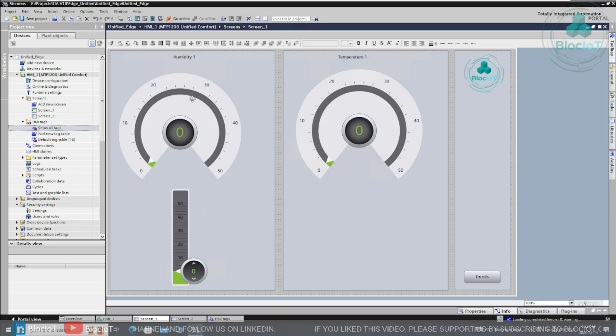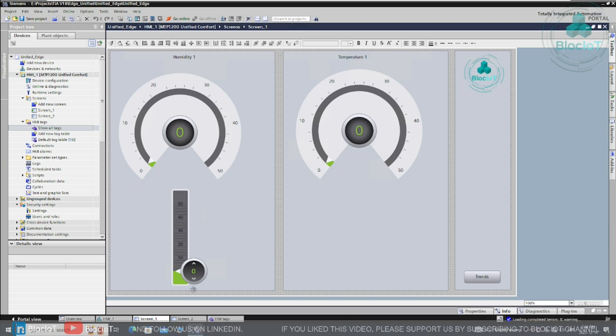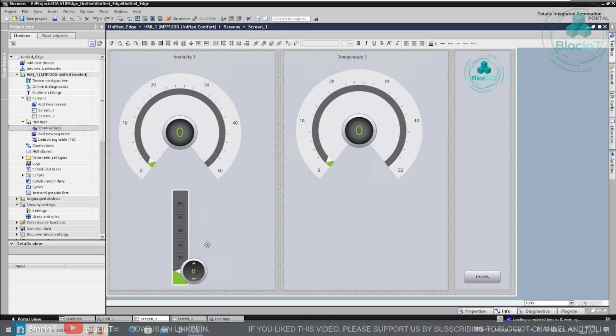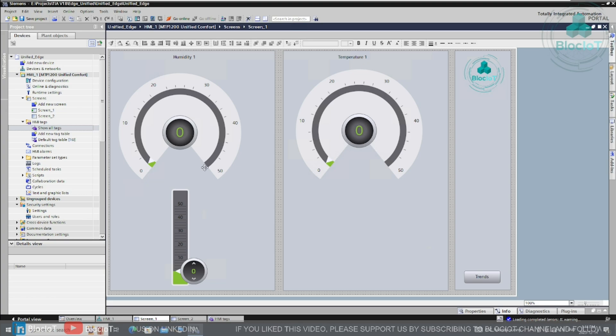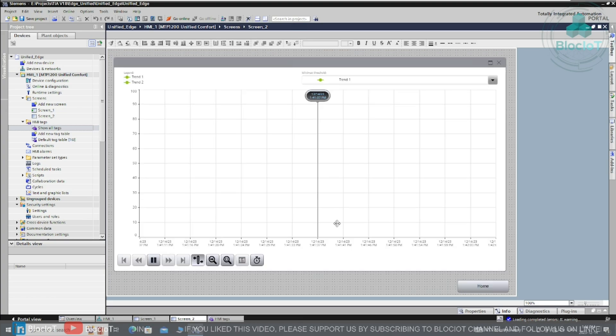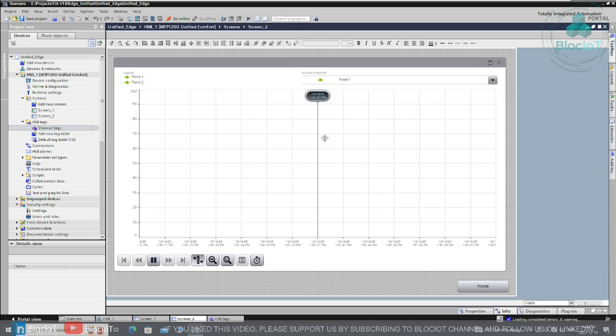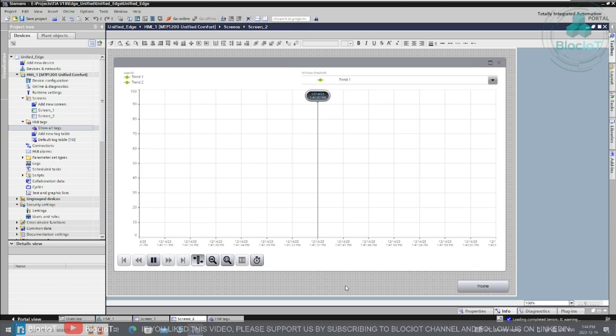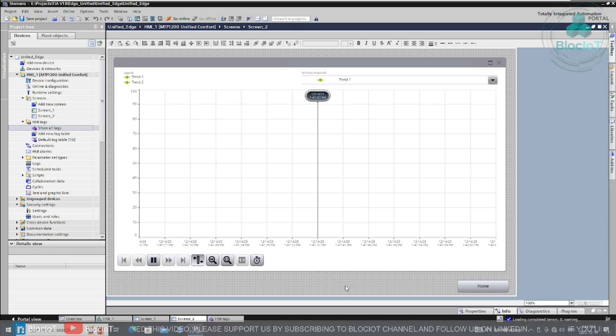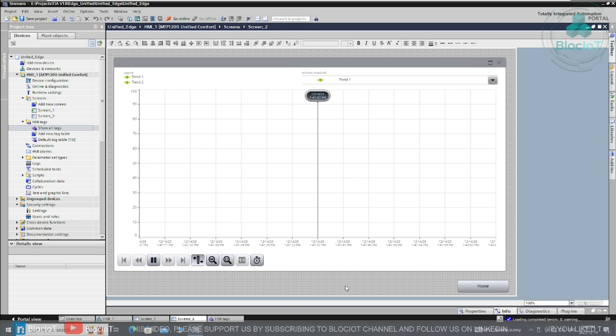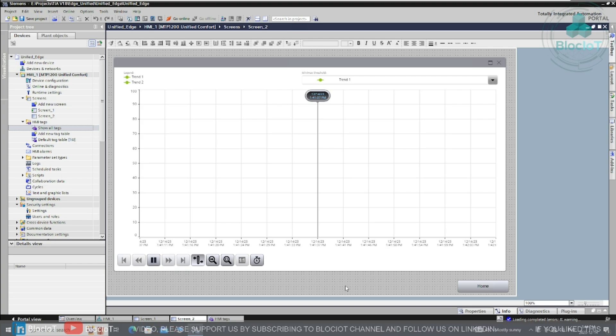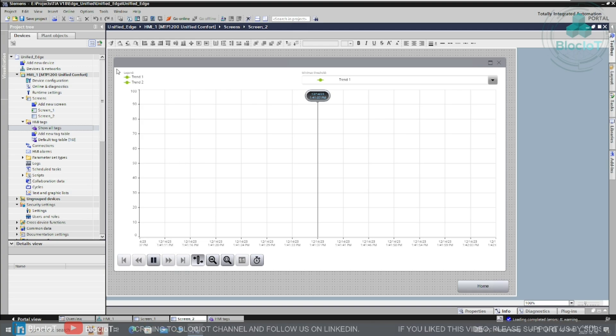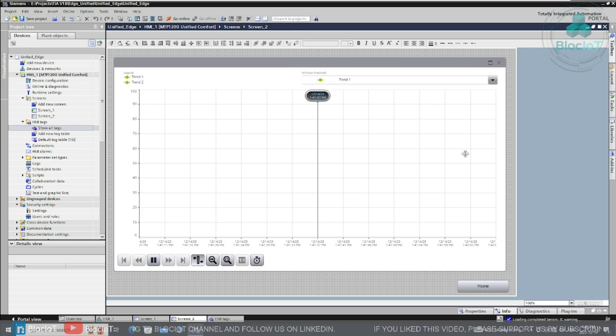In a nutshell, our analog input zero is connected to temperature one MQTT topic and that's what we are going to show on our HMI. On the left side we have a gauge for humidity and also a slider bar to just change the value or simulate some value because there's no physical device connected to this tag. The trend object simply shows the historical value of these two tags. As you can see the project is very simple. You don't need to be worried about anything about MQTT or industrial edge on TIA portal. You program your HMI in a traditional way. Once you have your sample project you just download to your unified comfort panel and we are ready for the next steps.